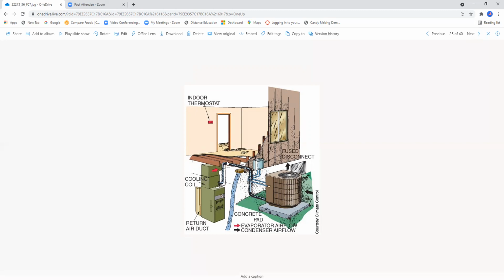And the ductwork, which it doesn't show here, appears to be hanging under these floor joists. Now you have your return located by where this connection is. It doesn't show it in this picture necessarily, but that return air is typically where you want the thermostat to be located. The reason is simple. We want to sense the actual air that is being returned to the unit. And this picture, by the way, can be found on page 1065 under 36.7.